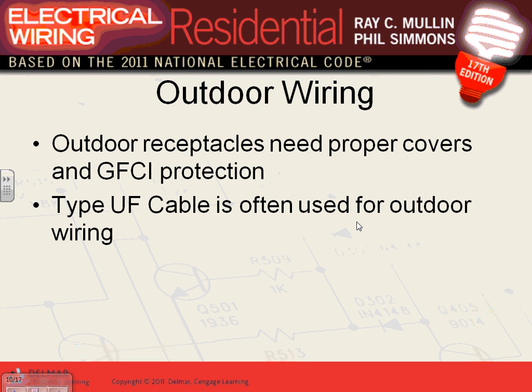So outdoor wiring, GFCI. You can use UF cable or you can use THHW conductors with conduit. Most likely in a house, guys, we use UF cable. UF cable is rated for two things: to be directly buried, no conduits. But when it emerges from the ground, you have to protect it though. Remember, when a cable emerges from the ground, you have to protect it from 18 inches below the ground up to 8 foot if it has to go that high. So you have to protect it when it emerges from the ground.